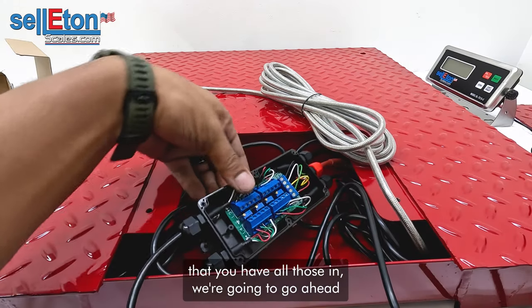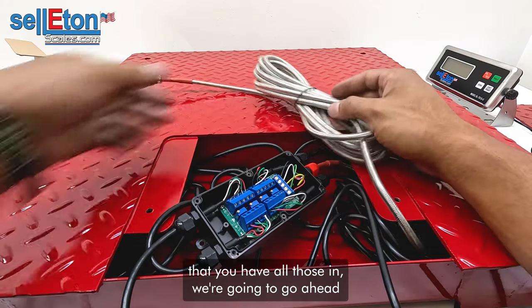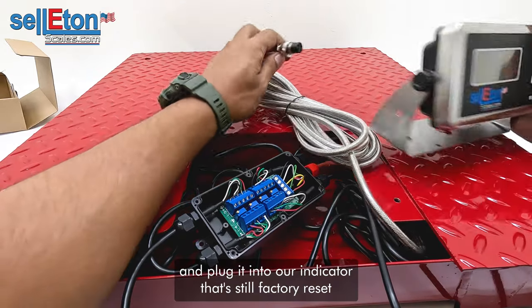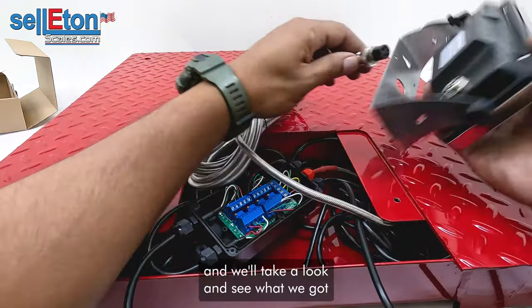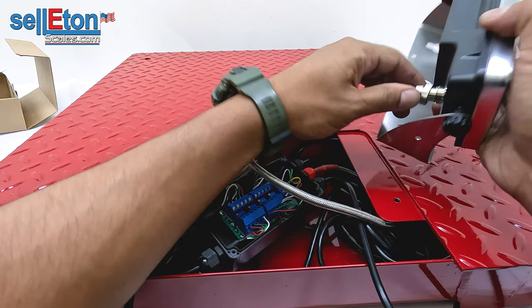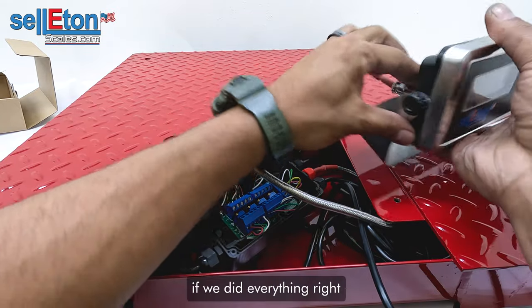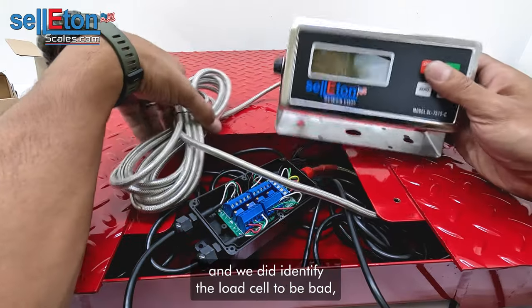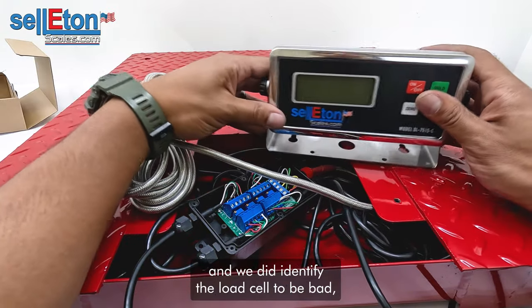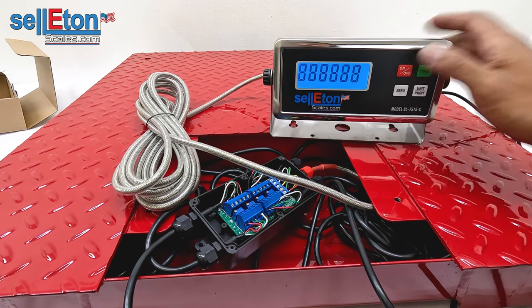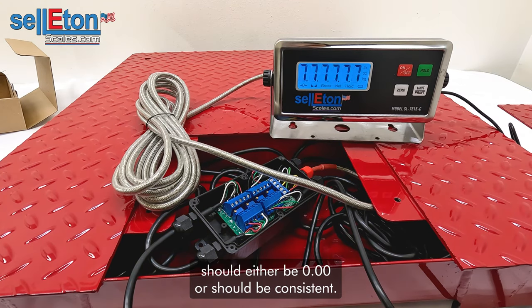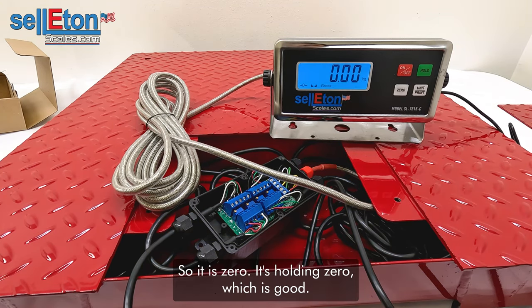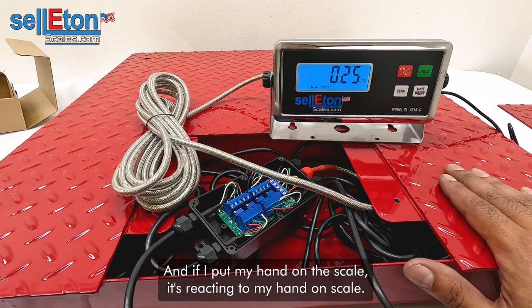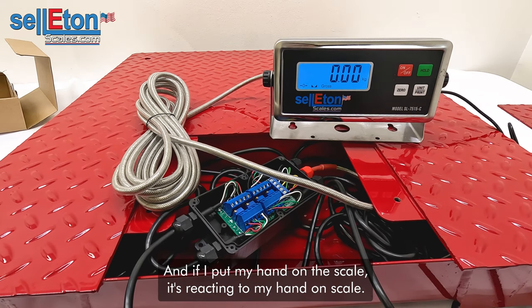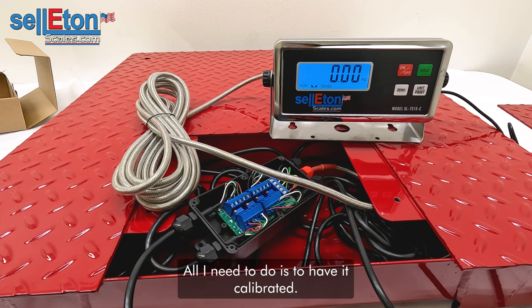Great. Now that you have all those in, we're going to go ahead and plug it into our indicator that's still factory reset. And we'll take a look and see what we got. If we did everything right, and if we did identify the load cell to be bad, then this should either be zero or should be consistent. So it is zero, it's holding zero, which is good. If I put my hand on the scale, it's reacting to my hand on the scale. So it looks like we have a fixed indicator. All I need to do is to have it calibrated.